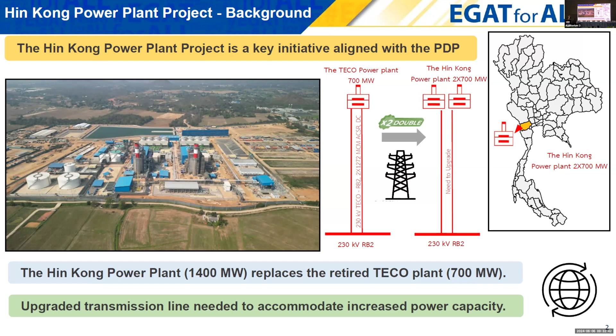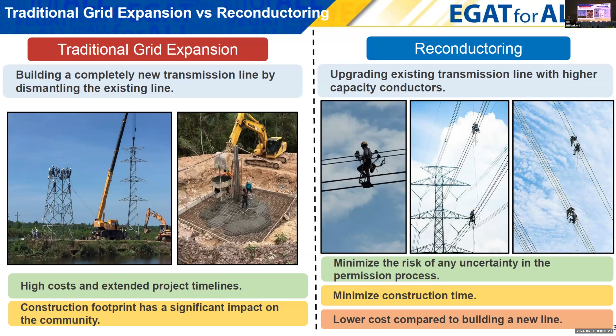The conductor size is 2 bundle of 1272 MCM ACSR. For the emergency case, N-1, it cannot transfer the double capacity to the grid. So we need to do something to solve this problem. This slide shows how to solve the problem. The first option is traditional grid expansion, increasing transmission line capacity by dismantling the old line before building an entirely new line. This process is very expensive and impacts the community. The second option is reconductoring, by replacing the conductor on the existing tower with a higher capacity one. This way minimizes the risk of uncertainty in the permission process, and minimizes construction cost and time compared to building a new line.